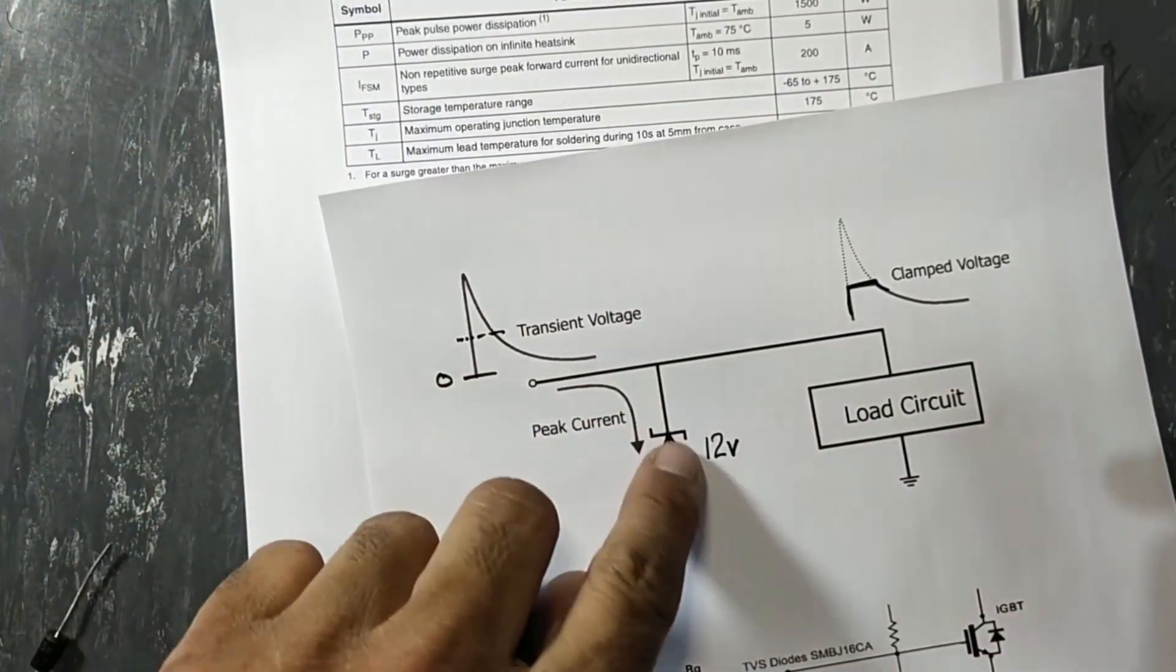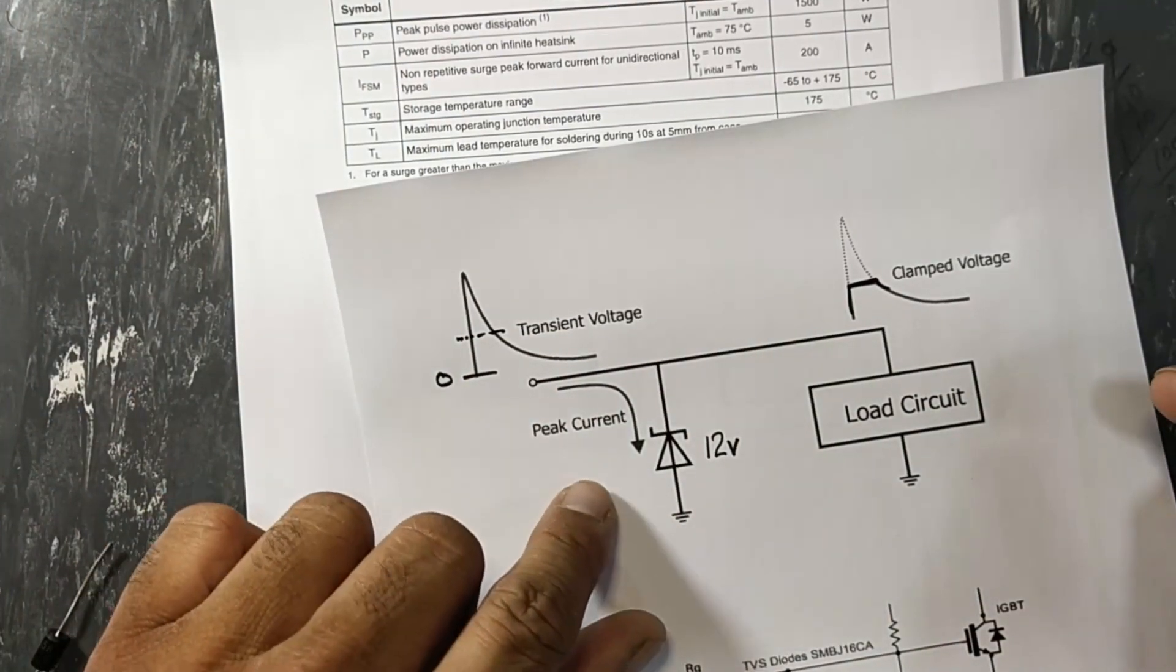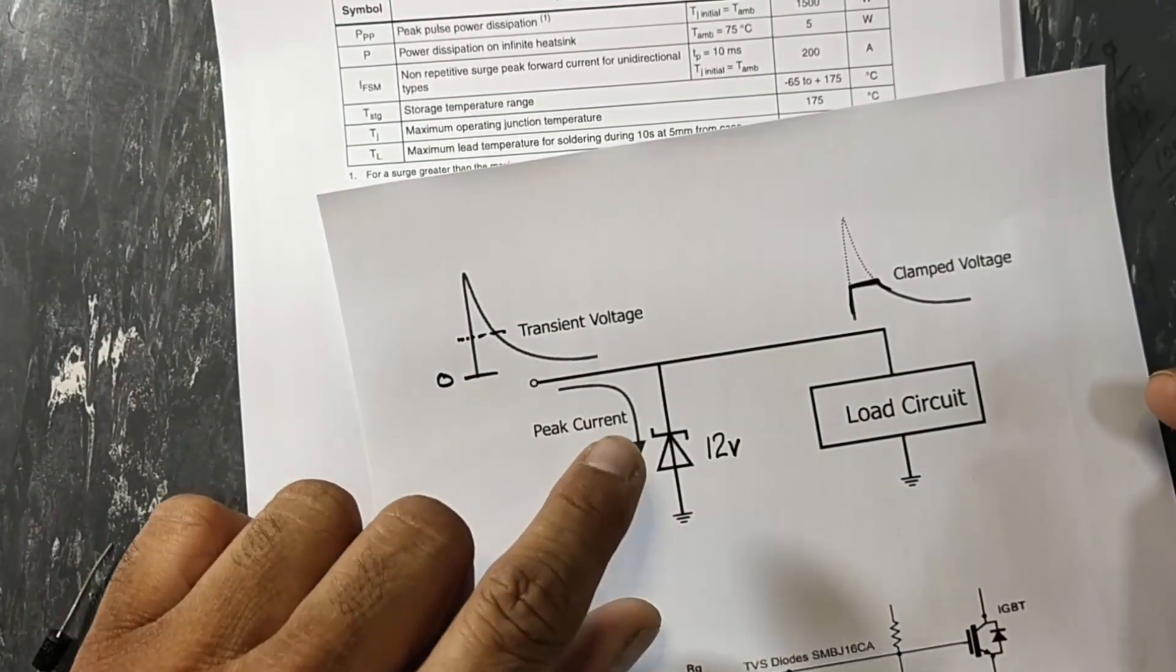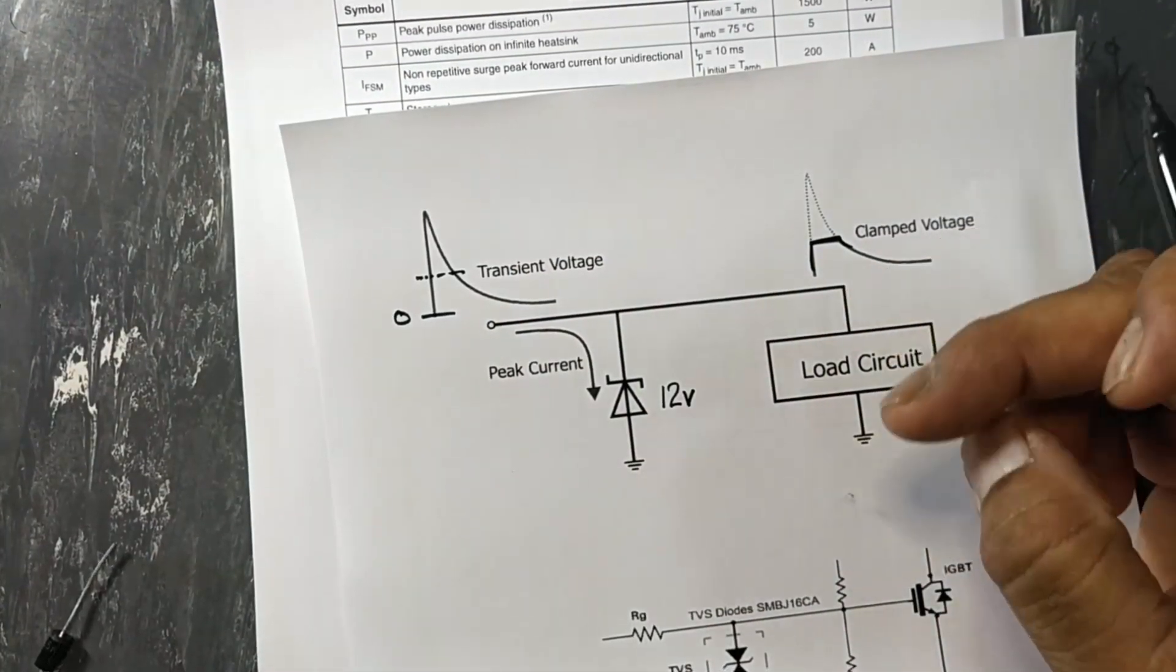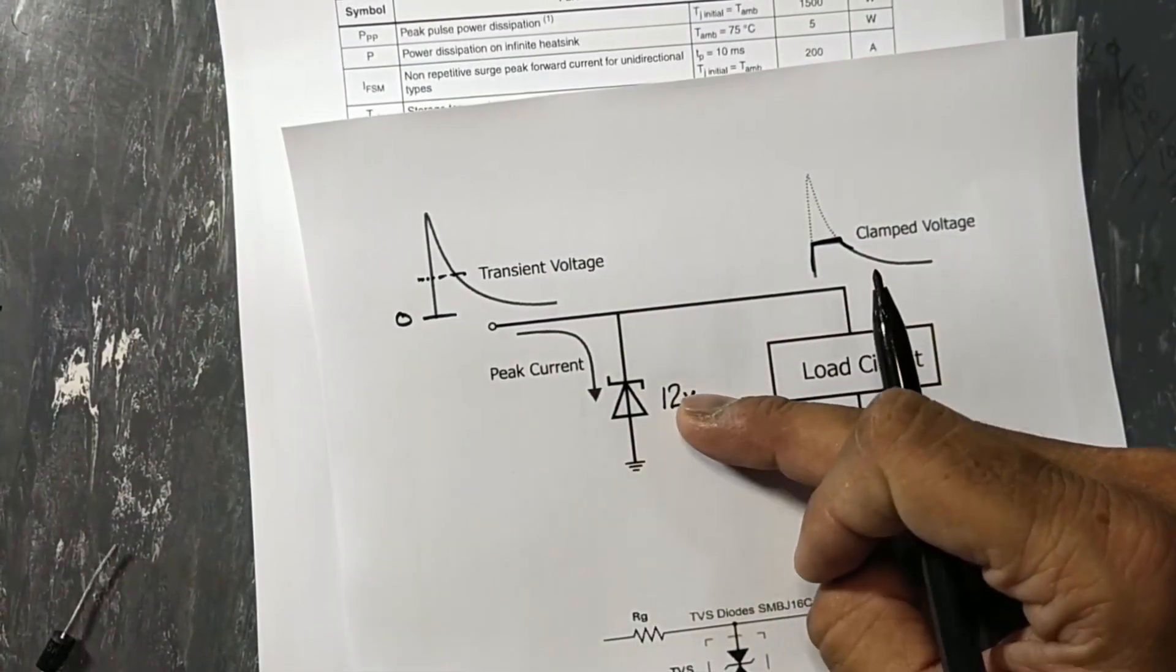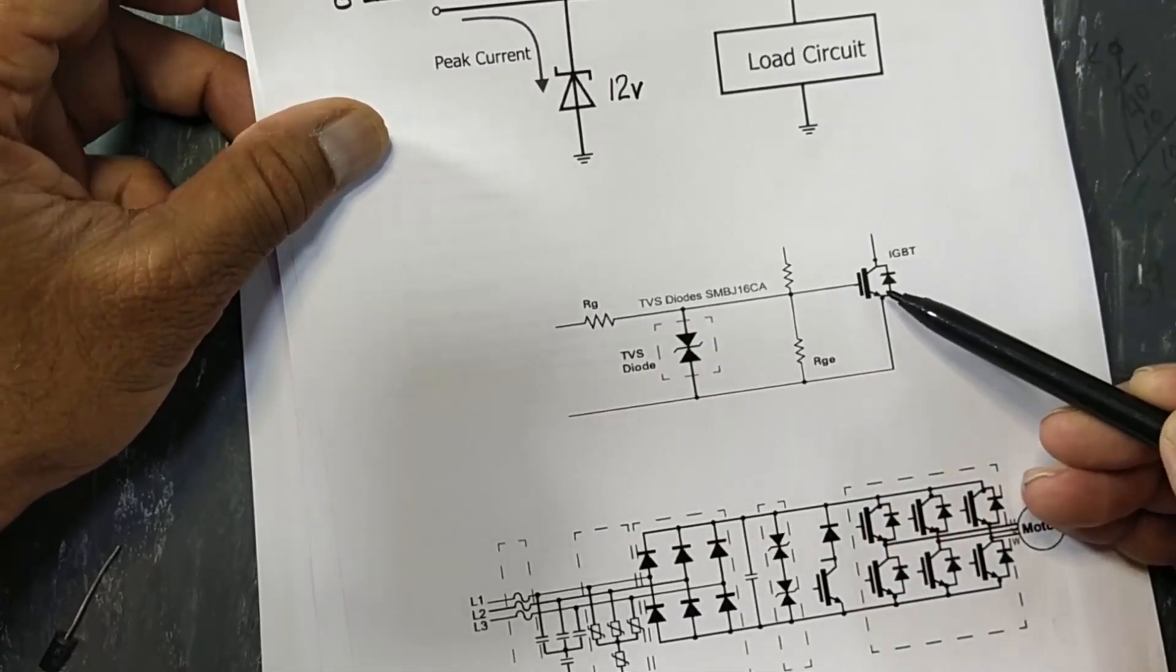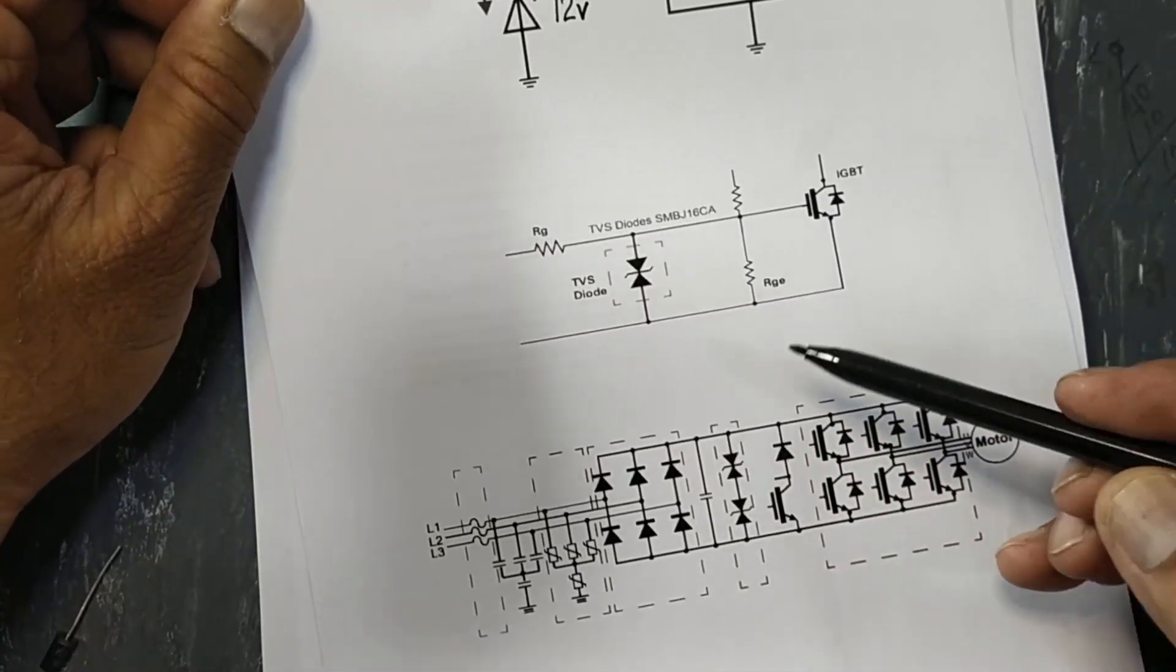And the upper voltage will be grounded. We can say it has similar to zener function, but it is a protection. Its junction is much wider compared to zener. Most of the time it is used for protection for IGBTs and VFDs for DC rails.